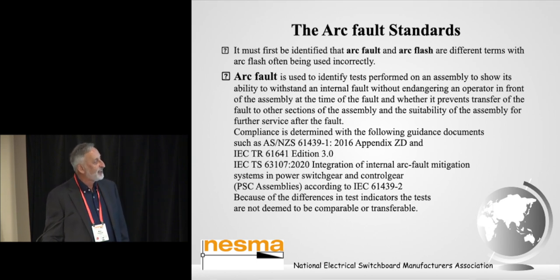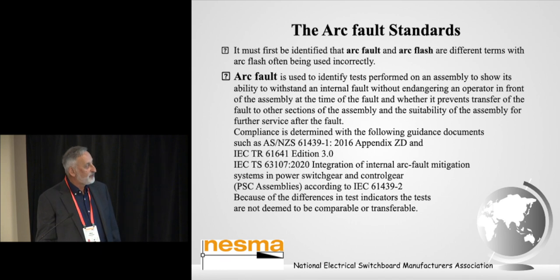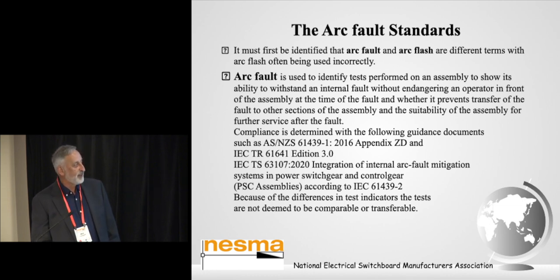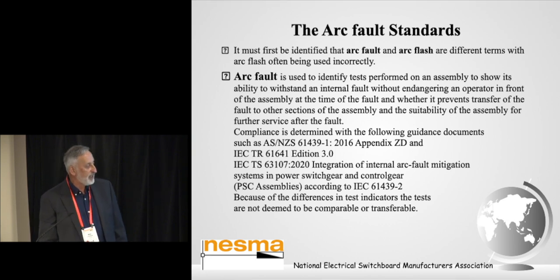Arc fault and arc flash are different terms, with arc flash often being used incorrectly. An arc fault is used to identify tests performed on an assembly to show its ability to withstand an internal fault without endangering an operator in front of the assembly at the time of the fault, and whether it prevents transfer of the fault to other sections of the assembly, and the suitability of the assembly after a fault for a further service. And compliance with that is usually determined by the guidance documents of AS/NZS 61439-1:2016 Appendix ZD and the IEC TR 61641 Edition 3.